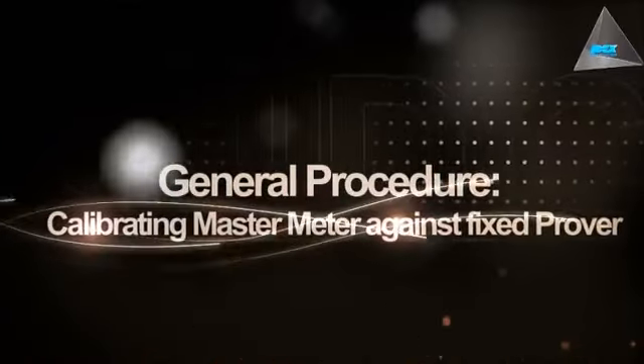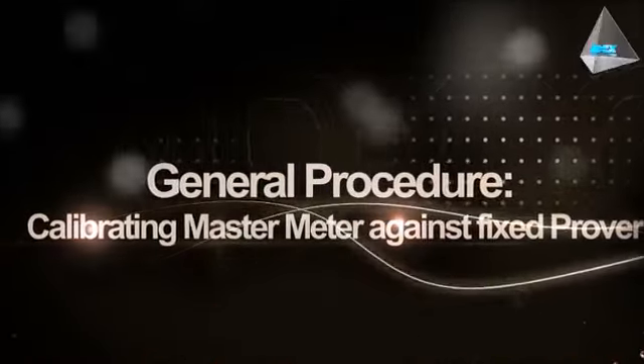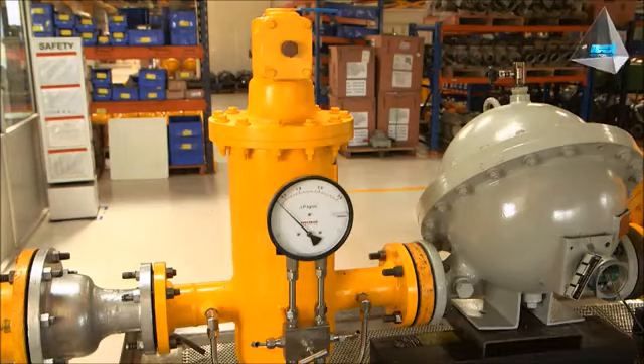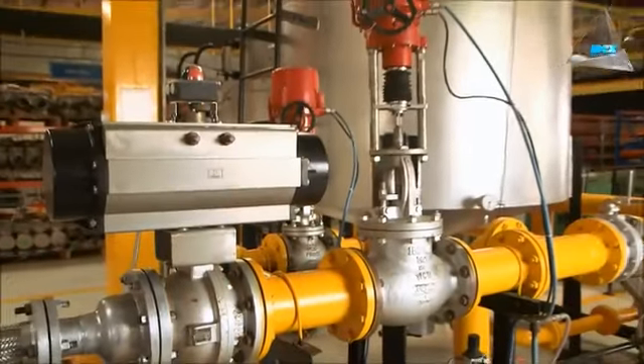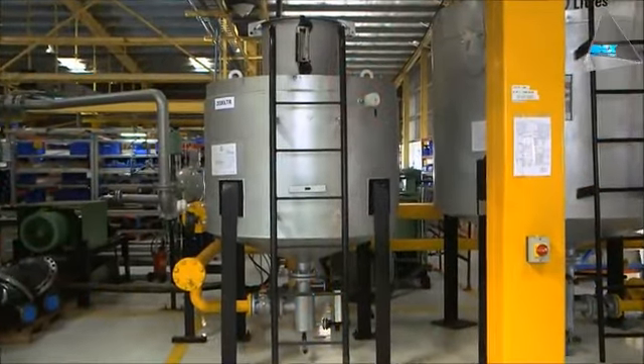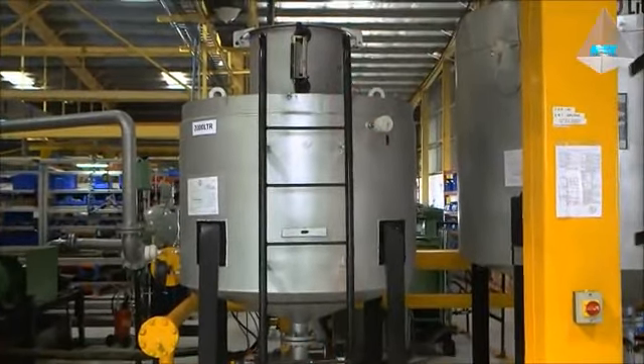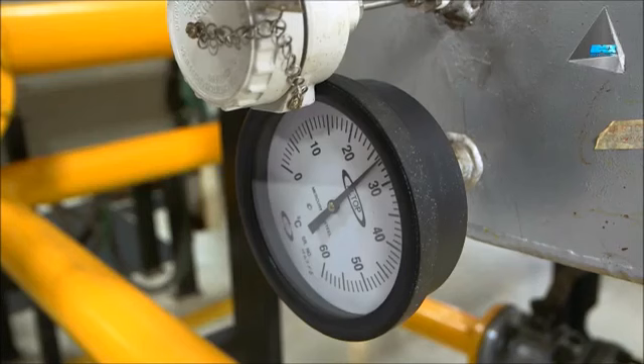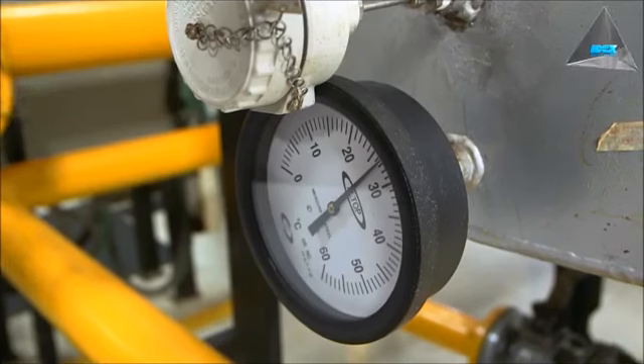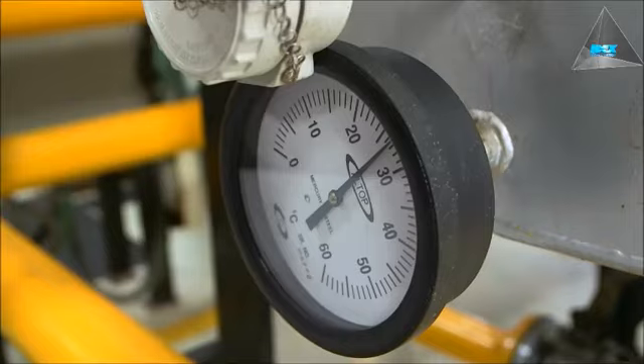General procedure for calibrating the master meter against a fixed prover. Mount the master meter in series with the prover in the pipeline carrying the liquid into the proving tank. The proving tank is filled once or twice to wet the surfaces and to remove the entrapped air. Check the temperatures and pressure. Ensure that these are stabilized during calibration tuning.